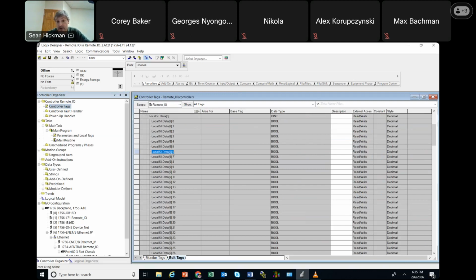So this confusing tag right here is going to be mapped to 1 PB. Okay, and then 1 PB is now part of the ladder scan. So on a scale of 1 to 10, do you fully agree that I can take this crazy looking thing right here and go into my input mapping sub and make it 1 PB? And then I can just use 1 PB in my program.